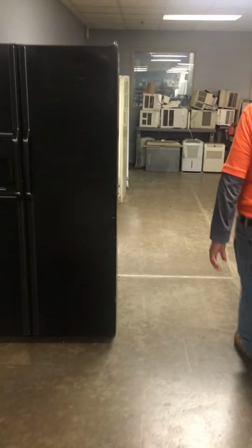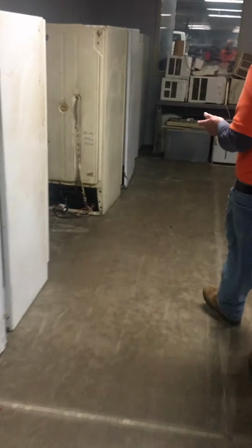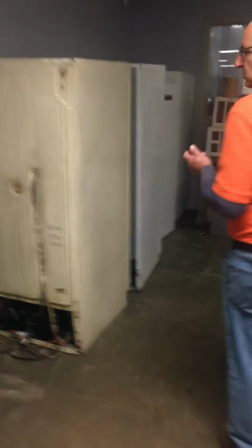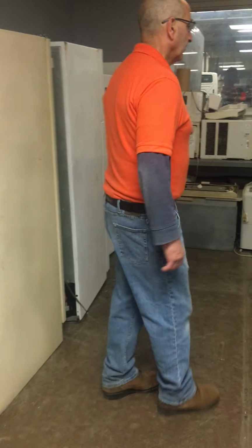I want to walk over here to show you that we're doing our domestic lab, so we do work on fridges. That's one of the things we start off with. We have to recover the refrigerant, change the oil in the compressor, braze it back in, and then do a standing pressure test. Then we do an evacuation until it goes below 500 microns, and then we recharge.